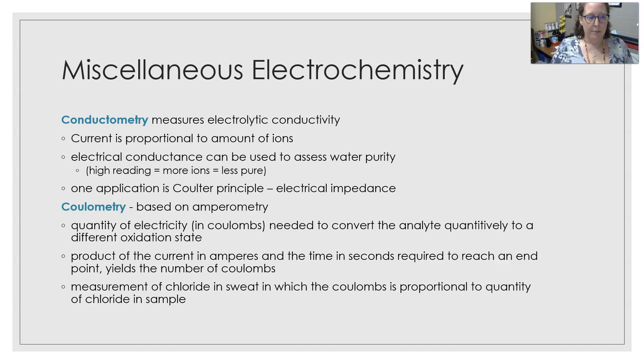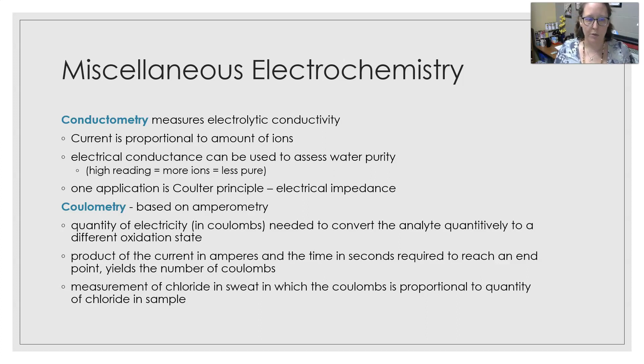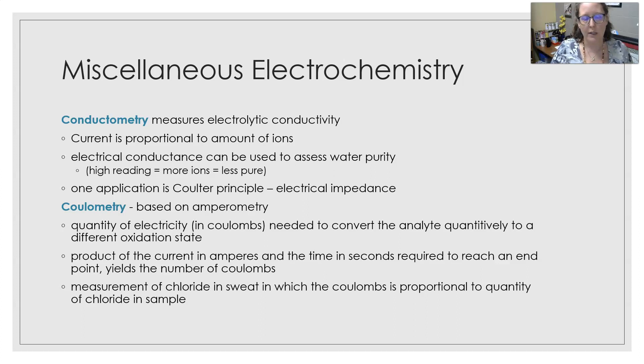Coulometry is based on amperometry — similar to the Clark PO2 electrode. The quantity of electricity in coulombs needed to convert the analyte quantitatively to a different oxidation state is measured. The product of the current in amperes and the time in seconds required to reach the endpoint yields the number of coulombs. This has been used in the measurement of chloride in sweat, where the number of coulombs is proportional to the quantity of chloride in the sample.